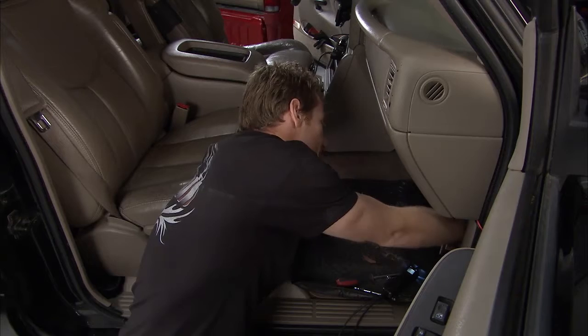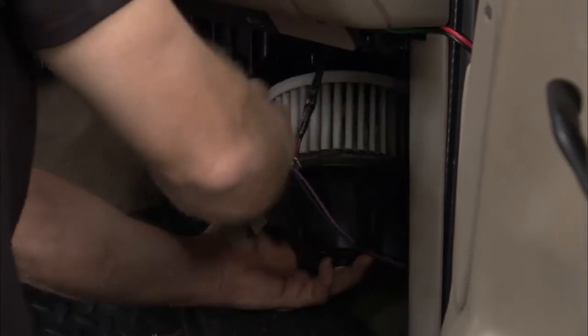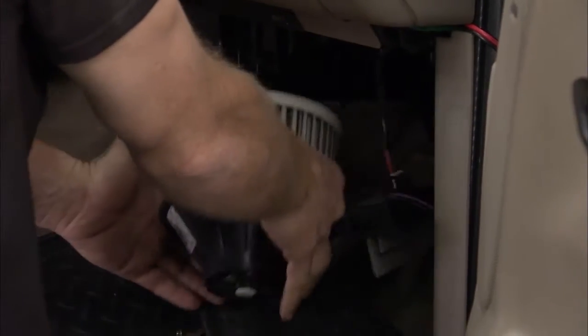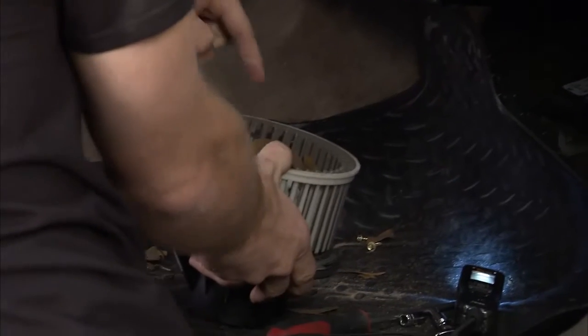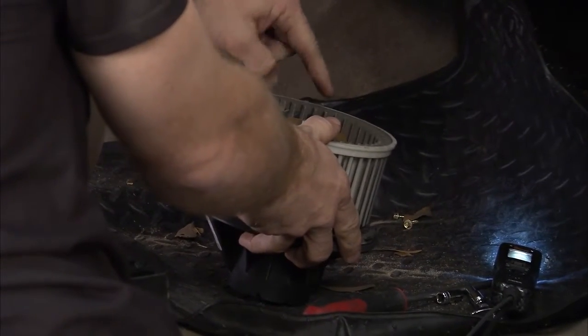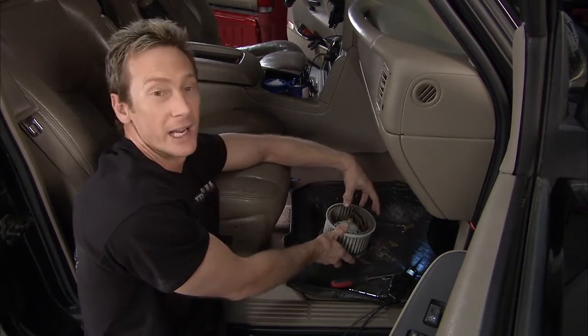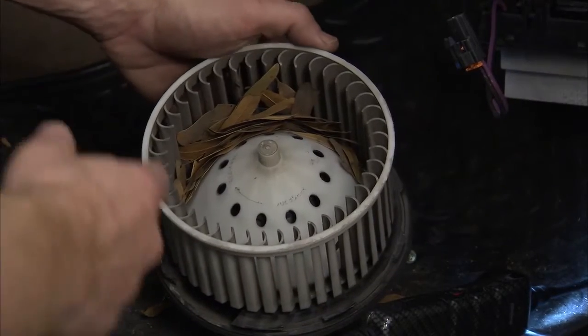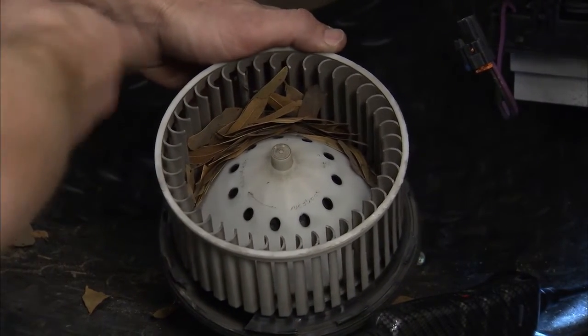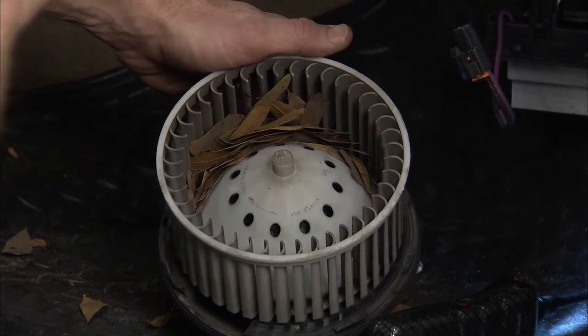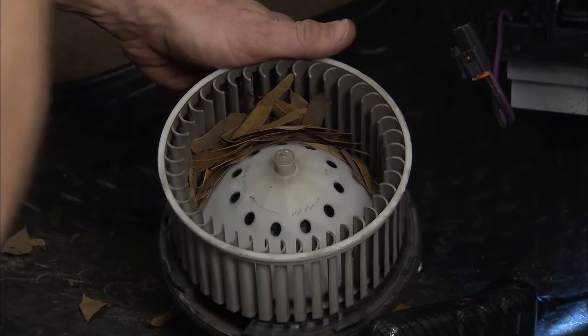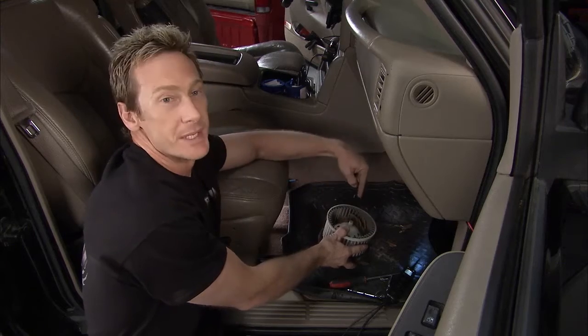If you pull the fan out, sometimes a visual inspection will tell you a whole lot. You get this thing out of the way, and you can see there are a ton of leaves and debris all sitting off to one side in this little fan. It's kind of like if you've got a bunch of clothes wet inside the washing machine or dryer — it's all side-loaded. When it starts to spin around in a circle, it jumps all around the place and vibrates. That's exactly what's happening right here.